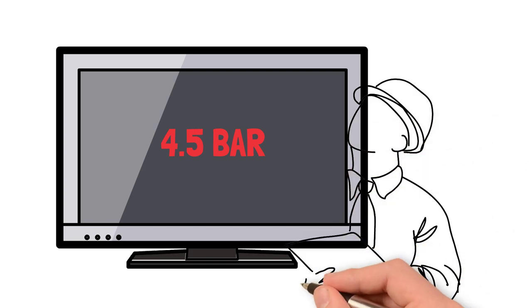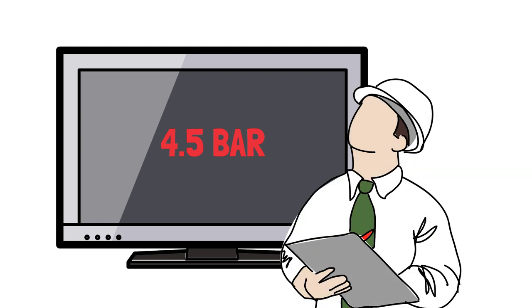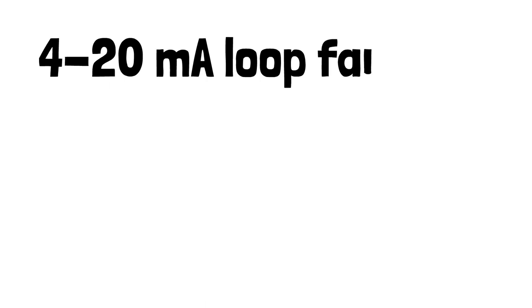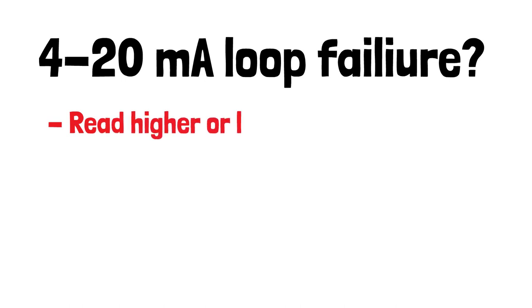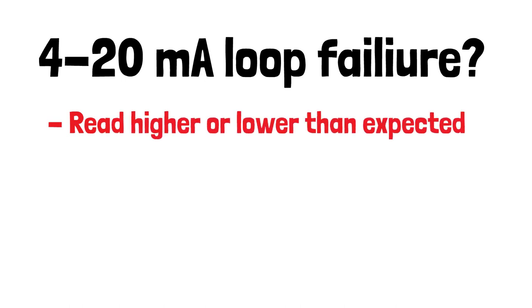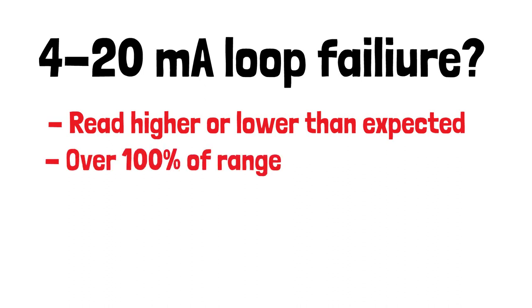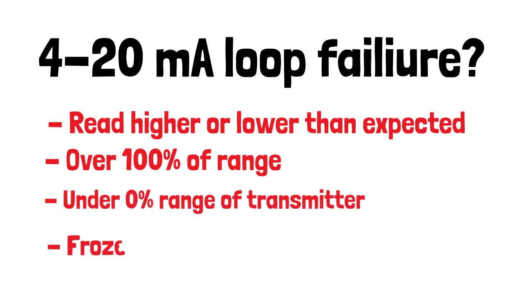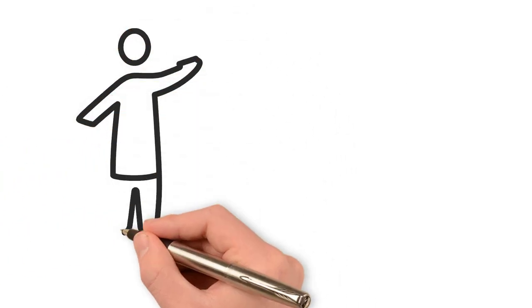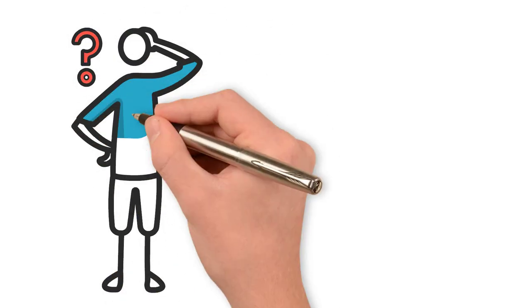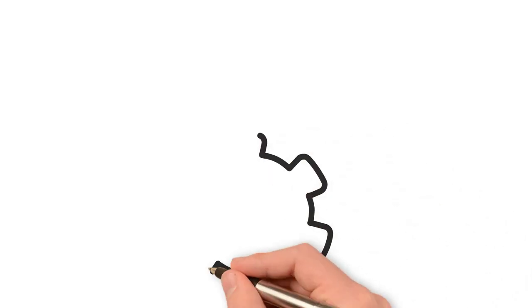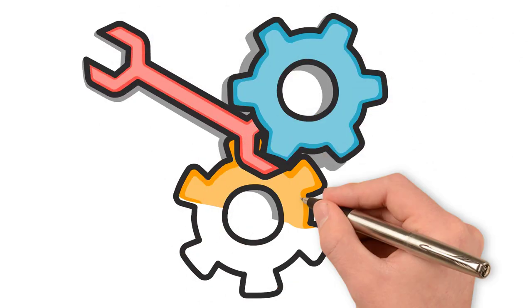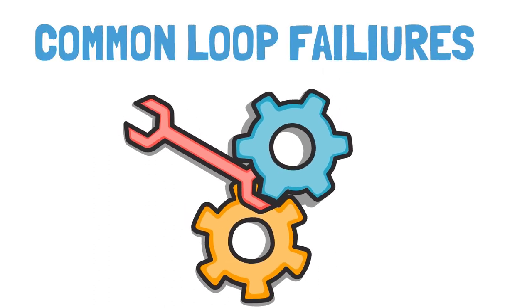This is fairly representative of what you might find out there on various sites across different industries. The typical 4 to 20 milliamp loop may fail in a few different ways. The common faults the operator may report are: an instrument reading higher or lower than expected, an instrument failing by going over the 100% range value or under the 0% range, or a process instrument reading frozen over long periods of time. Even though there are only a few ways the transmitter can show an issue to the operator, there are lots of different causes of these faults. I'm going to cover some of the most common types of 4 to 20 milliamp loop failures common to all electrical transmitters.